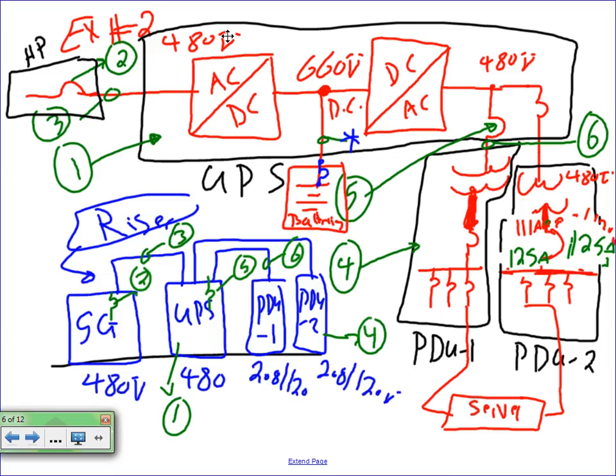This is what you guys have, our system. We have our switchgear, and we took a feeder from the switchgear to feed our UPS system. From our UPS system, uninterruptible power supply, we took 2 feeders. One is going to feed PDU1, one is going to feed PDU2, and all these correlated numbers, hopefully they will correlate with the schematics or the wiring as well as the physical. I think we have the transformer ahead of the UPS in the examples in the lecture. Yeah, you're absolutely right.